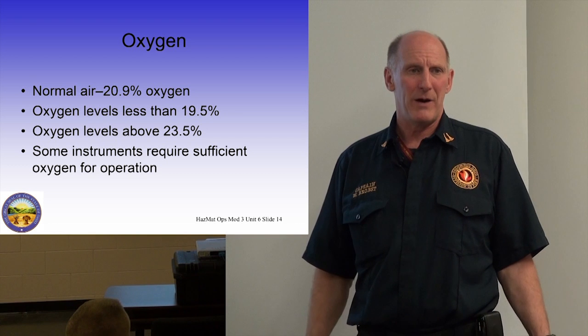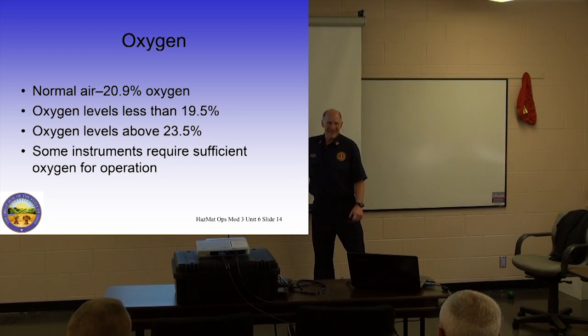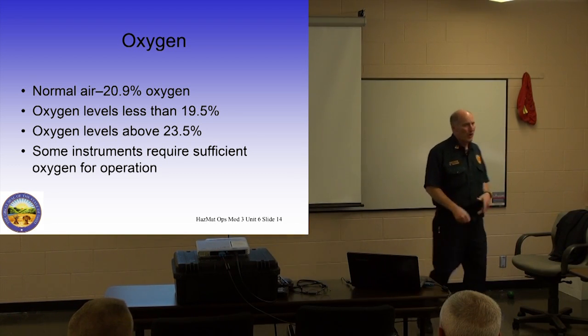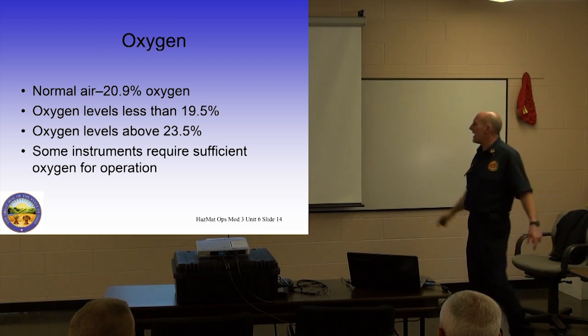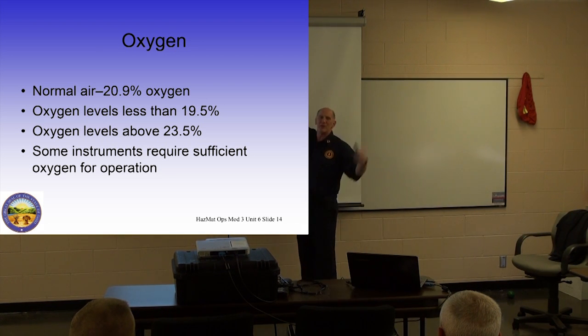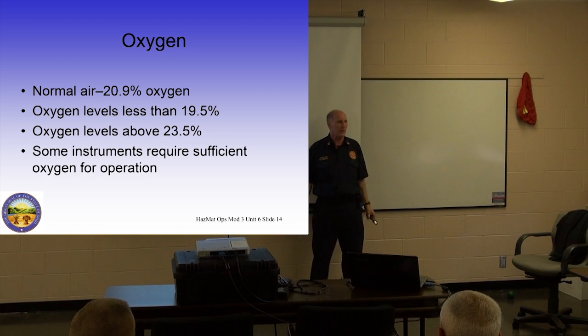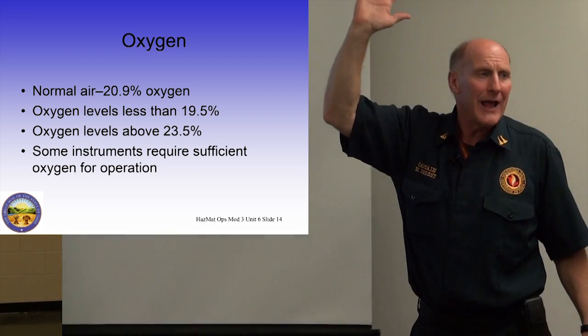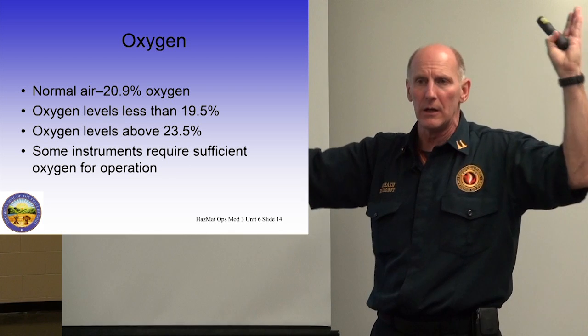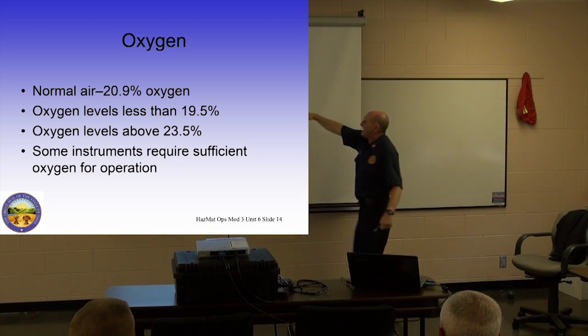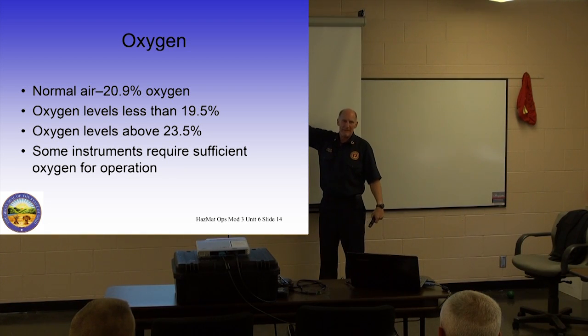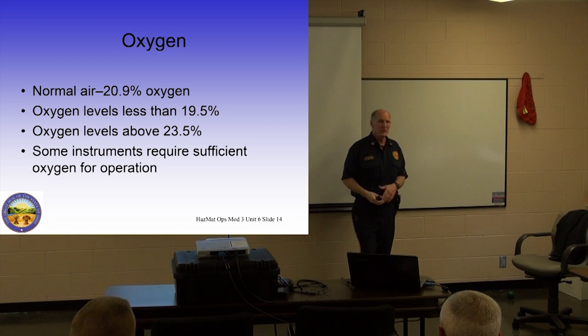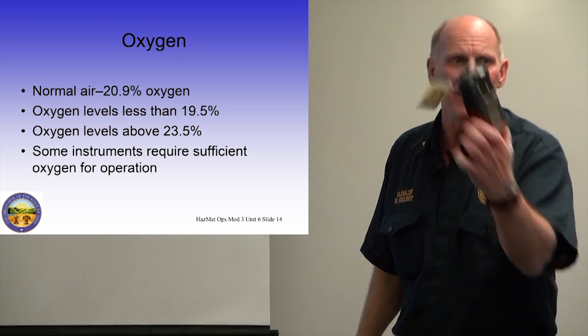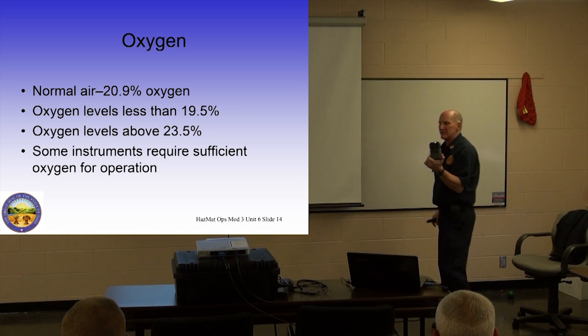But it's IDLH by OSHA standards. Excess oxygen. The high oxygen alarm is 23.5%. Well, the high oxygen alarm is 23.5% because OSHA says there's a law that says set it at 23.5%. At 23.5%, O2 becomes IDLH, immediately dangerous to life and health. It's a legal requirement. It does not have anything really to do with our health. It's got more to do with the inaccuracy of the instrument in high O2 areas.